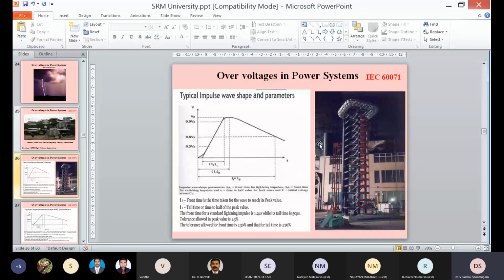Coming to the lightning impulse withstand voltage, or lightning impulse voltage, we already know that when the system voltage is up to 245 kV, power frequency fault and lightning impulse fault are significant. How to create it and how the wave shape should be, that is the critical condition. When I say lightning impulse voltage, the standard defines that it should have a front time of 1.2 microsecond and a tail time of 50 microsecond. The tolerance for the peak value is plus or minus 3%. The tolerance for the front time is plus or minus 30%. And the tolerance for the tail time is plus or minus 20%.